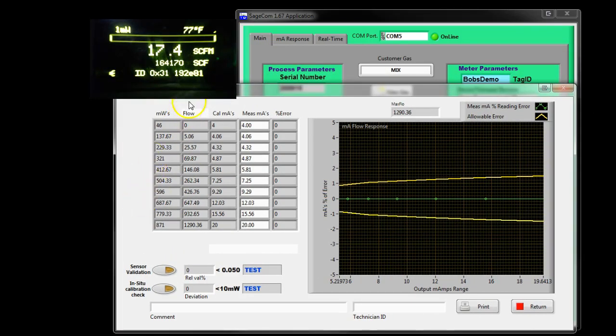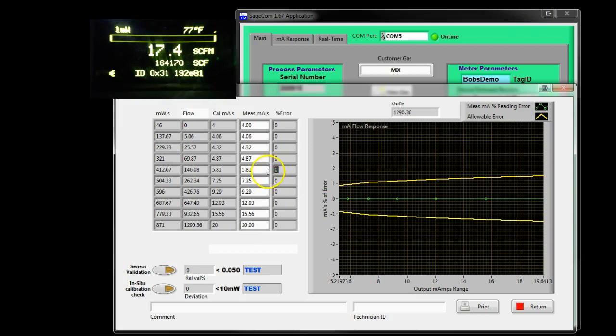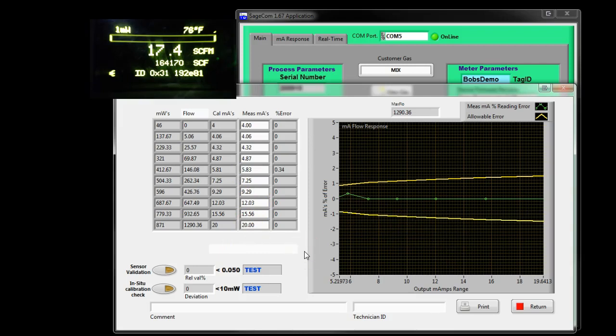Notice, the linearization here looks at the raw milliwatts versus the flow rate, did a random generation of different readings, 4 to 20, and finally the milliamps. By the way, if you don't trust a reading, put your fluke on the output and let's say you think it's 5.81 and it turns out to be 5.83. So, if I make a change and put in 5.83 because my fluke's reading that, simply type in the number that fluke's reading, press the return key, a little bit of an error, but certainly within spec, the yellow lines are our spec.